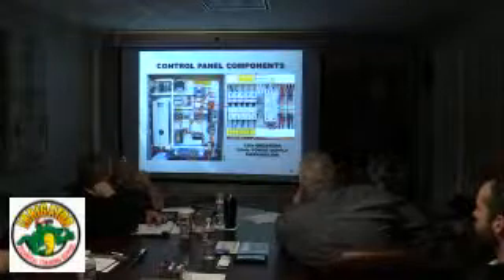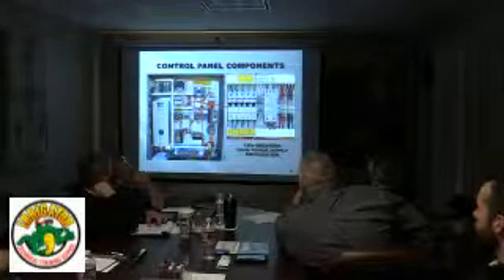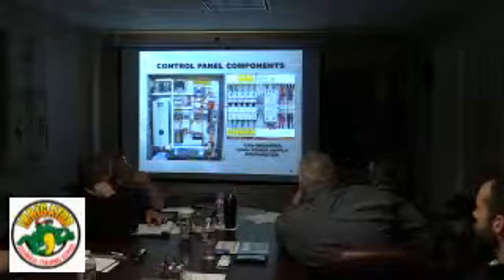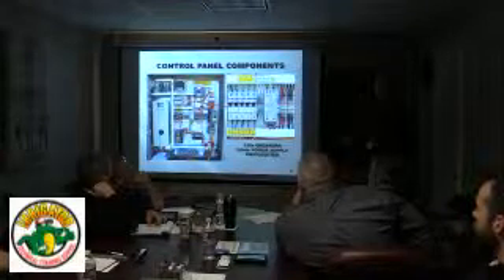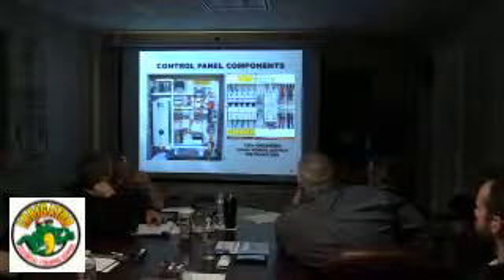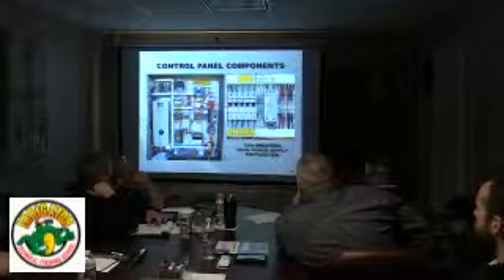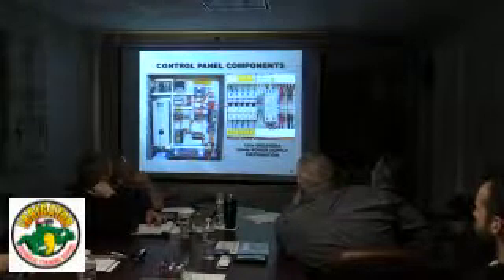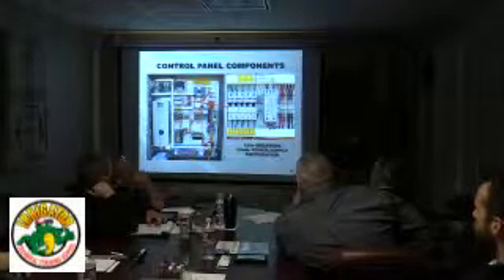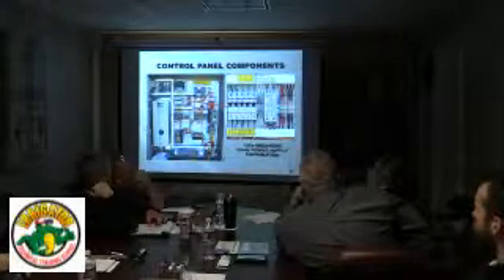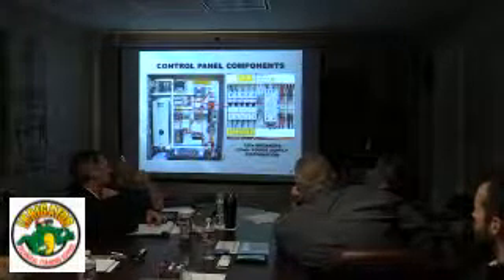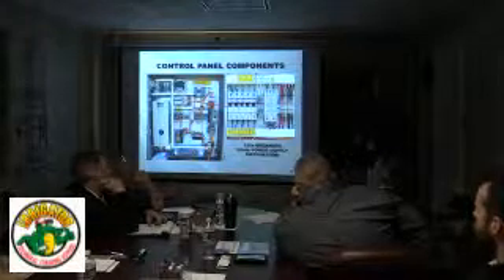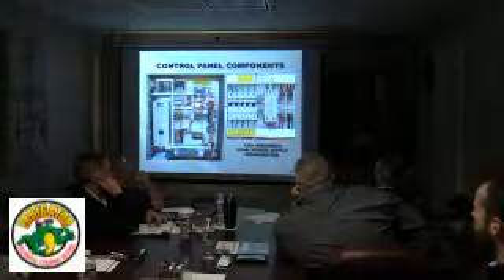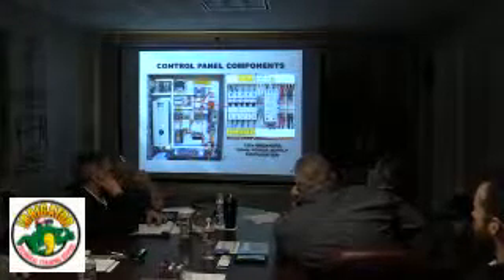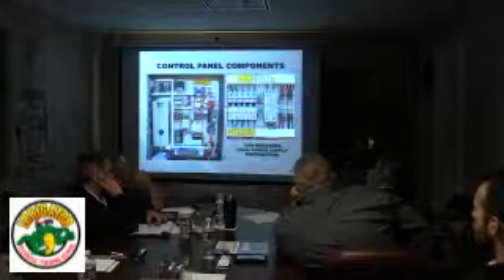One thing to keep in mind that I see quite often is if this power supply goes out, you're not going to get a touch screen, a PLC, everything's going to appear like it's dead. You open this door, this little green LED should be on, but it's off, and at least once or twice a year I get somebody say, send me a new power supply. You know, it's dead. I measure 120 up here, but I'm not getting 24 volt DC down here. So of course you'd think it's the power supply right away.